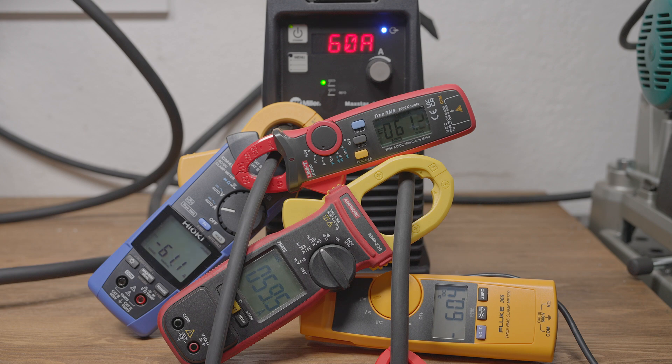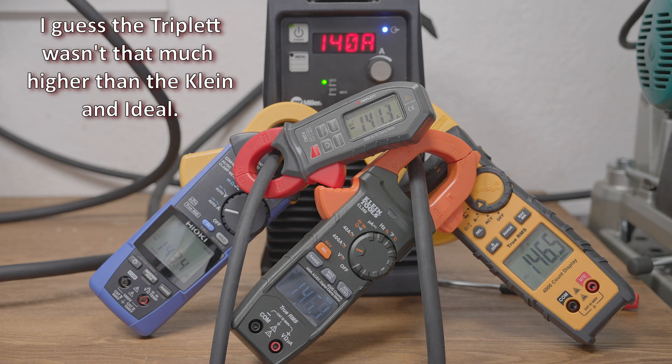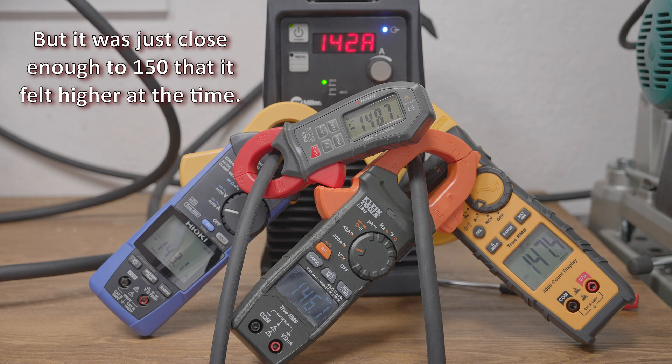The first group of meters all read pretty close. My old amp probe reads an amp or two lower than the rest, but it's probably within its accuracy spec. The readings on some jump around a bit more than others, but at both 60 amps and 140 amps, all of these meters read within a few amps of each other and the meter on the welder. The Triplett meter read a bit high when running at 140 amps — I didn't realize it was reading quite as high as it was, or I'd have included it in the 220 amp testing later. The Ideal and Klein meters read a few amps high, but overall pretty stable and not too far off.